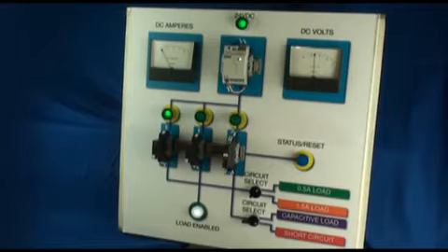As you can see, we have three 1 amp circuit breakers mounted on our panel. Breaker 1 is a TMC1 with the M1 trip curve. Breaker 2 is a 1 amp TMC with the F1 trip curve. And breaker 3 is our new electronic ECE circuit breaker.